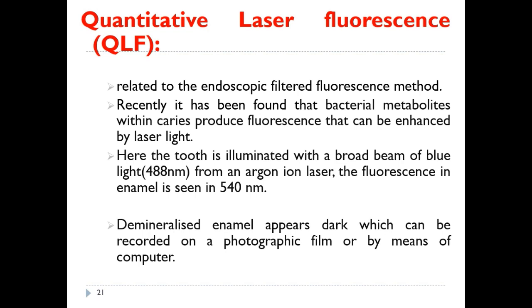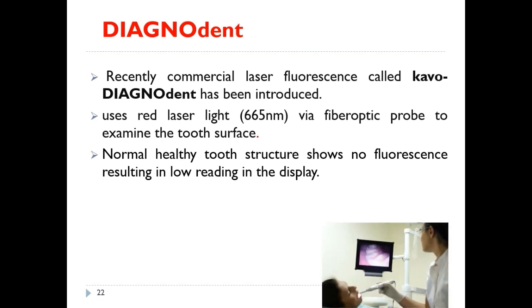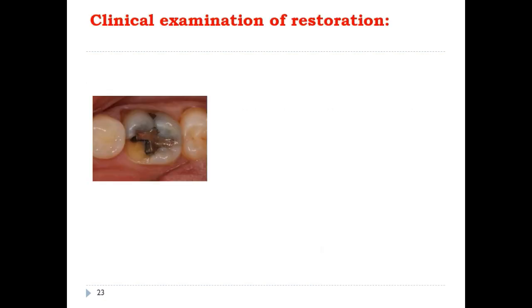Quantitative laser fluorescence (QLF) is related to the endoscopic filtered fluorescence method. Bacterial metabolites within caries produce fluorescence enhanced by laser light. The tooth is illuminated with a broad beam of blue light at 488 nm from an argon ion laser; fluorescence in enamel is seen at 540 nm wavelength, and demineralized enamel appears dark, recorded on photographic film or by computer. DIAGNOdent, a commercial laser fluorescence device by KaVo, uses red laser light at 665 nm via a fiber optic probe; normal healthy tooth structure shows no fluorescence, resulting in a low reading.